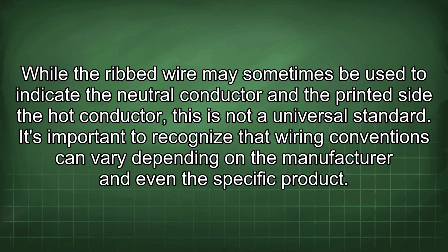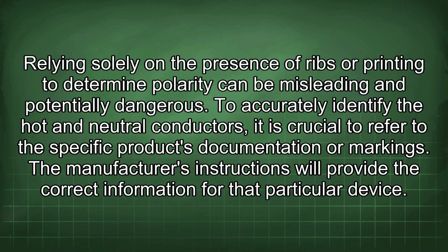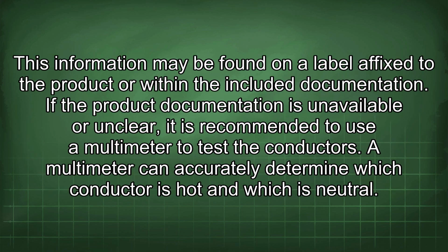It's important to recognize that wiring conventions can vary depending on the manufacturer and even the specific product. Relying solely on the presence of ribs or printing to determine polarity can be misleading and potentially dangerous. To accurately identify the hot and neutral conductors, it is crucial to refer to the specific product's documentation or markings. The manufacturer's instructions will provide the correct information for that particular device. This information may be found on a label affixed to the product or within the included documentation.